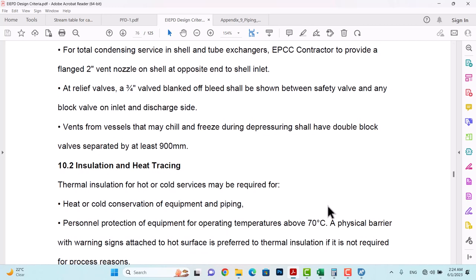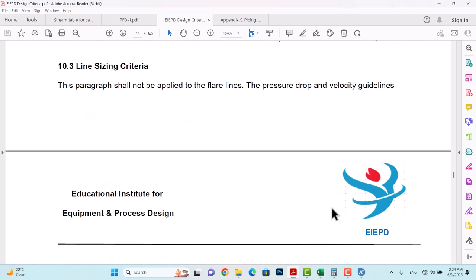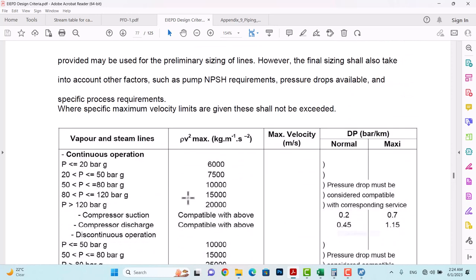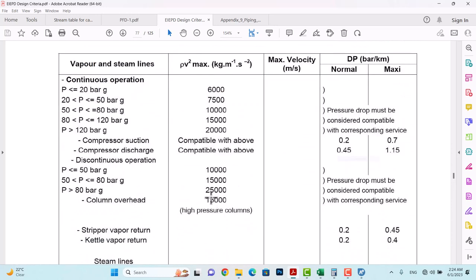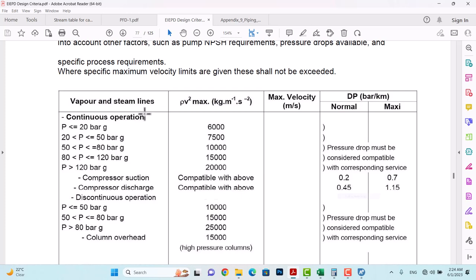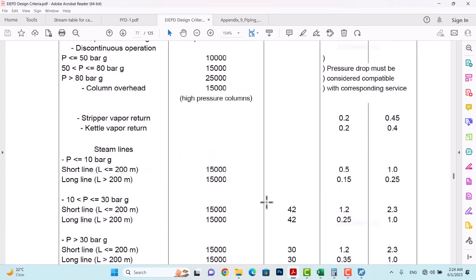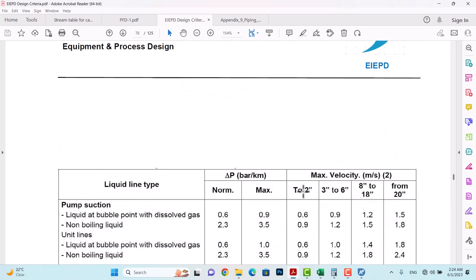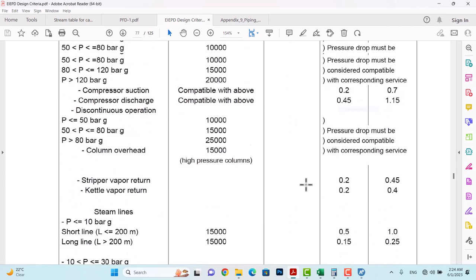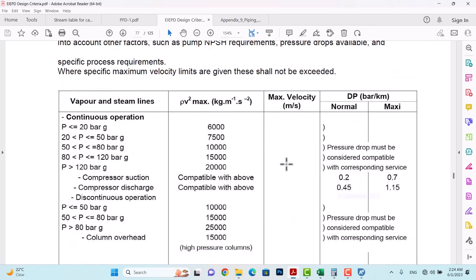At first, we became familiar with these tables for vapor and steam lines, and of course another table for liquid line type. We stated that these tables and the values are our basis for line sizing criteria.